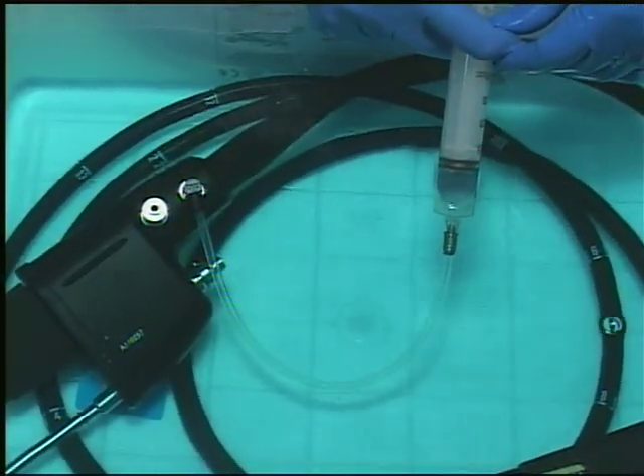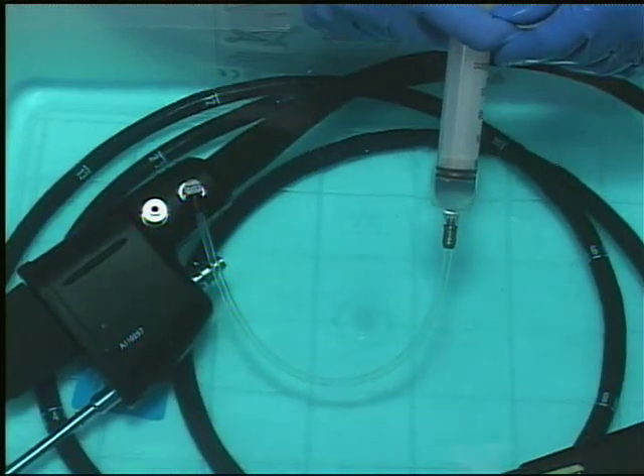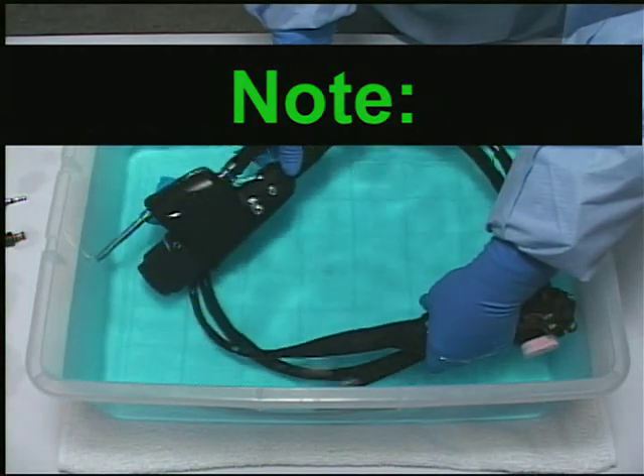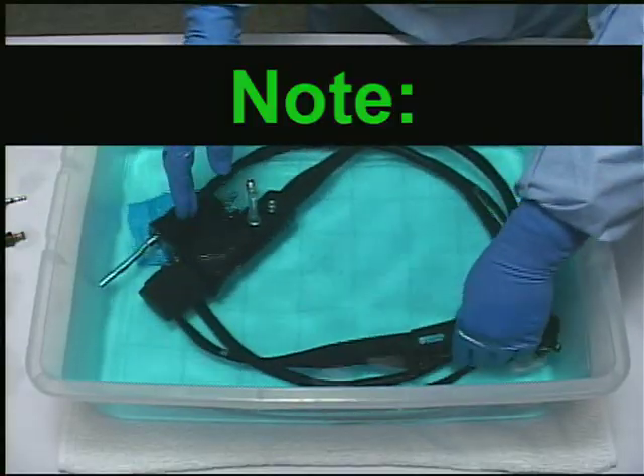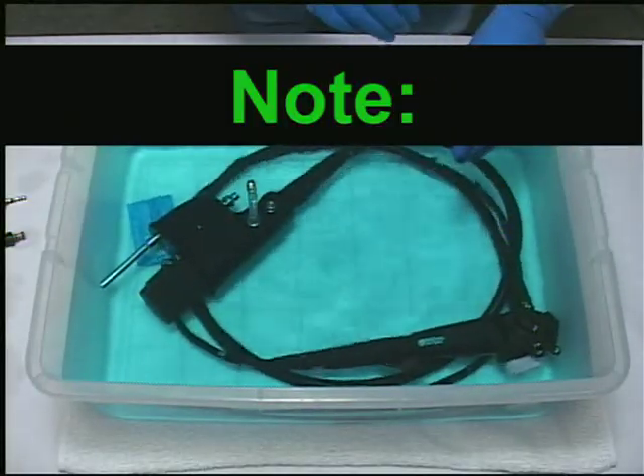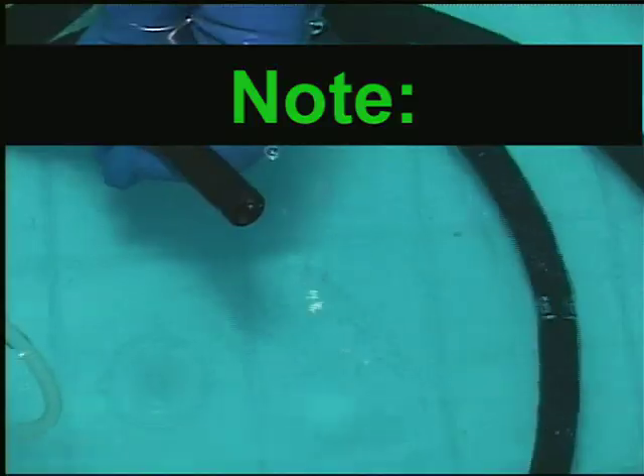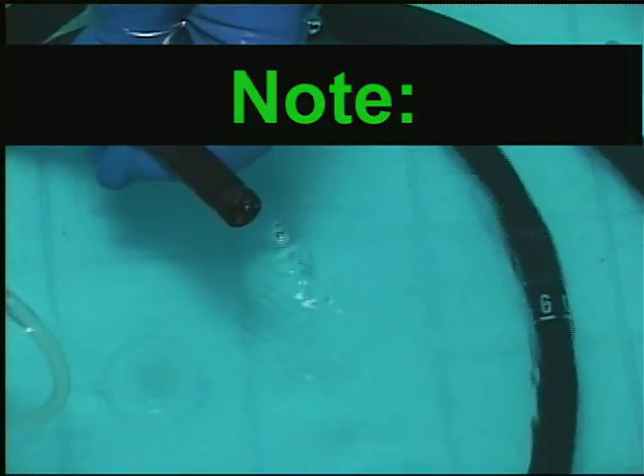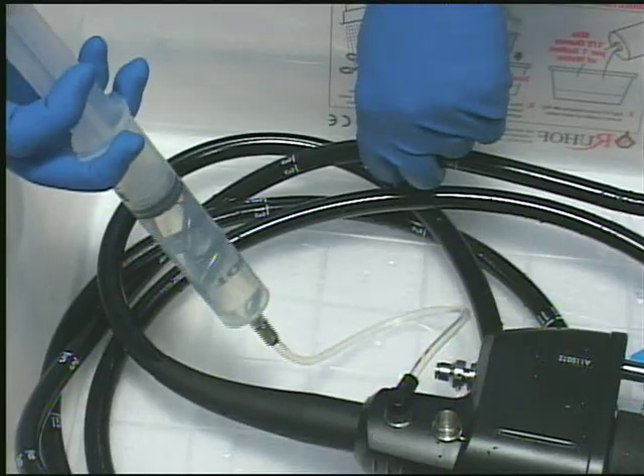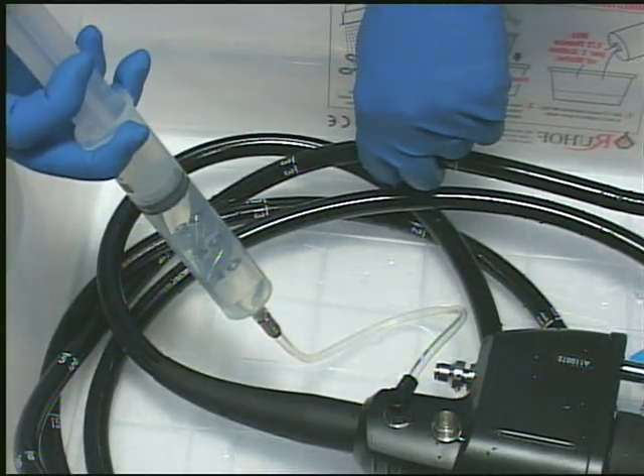Providing the entire instrument is completely immersed in disinfecting solution, all water jet components may be removed from the scope and soaked in the solution. Note: ensure proper contact of all exposed surfaces to the disinfectant. Follow by thorough rinsing and drying of the water jet channel. As with all internal channels, alcohol followed by forced air should be used to facilitate drying.